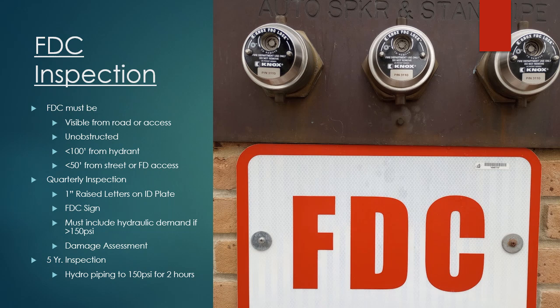During a quarterly inspection, you should look at the lettering that designates what the FDC feeds—either a sprinkler, a standpipe, or both. It should be labeled on the back plate. There should also be an FDC sign, red on white, and if the hydraulic demand of the system is greater than 150 psi, that should tell you what that's for. Then you just want to make sure everything functions and there's no obvious damage.